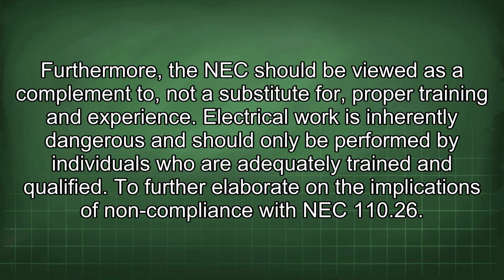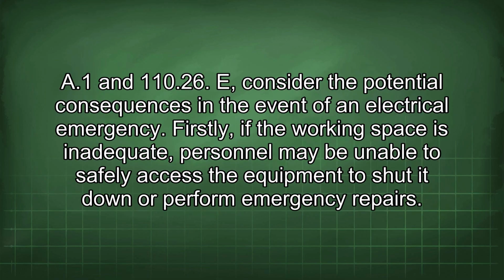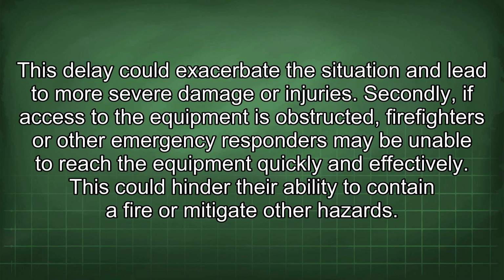To further elaborate on the implications of non-compliance with NEC 110.26 A1 and 110.26 E, consider the potential consequences in the event of an electrical emergency. Firstly, if the working space is inadequate, personnel may be unable to safely access the equipment to shut it down or perform emergency repairs. This delay could exacerbate the situation and lead to more severe damage or injuries. Secondly, if access to the equipment is obstructed, firefighters or other emergency responders may be unable to reach the equipment quickly and effectively. This could hinder their ability to contain a fire or mitigate other hazards.